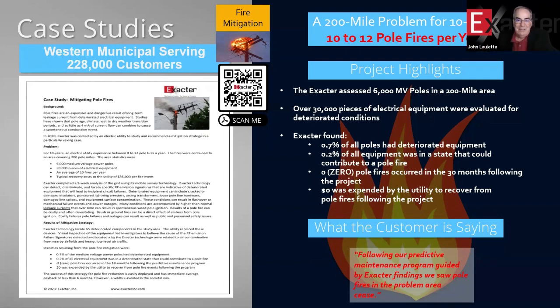And what we learned was this 200 miles of line was near a very large airport. So it was probably, like Mike was mentioning earlier, contaminants from airplane engines that were going over the line as they took off and landed. So they're not going to change that. So now we've got to figure out something better to do. And the better thing to do is to monitor the line for these partial discharge events, remove the equipment, and avoid the problem of pole fires altogether.